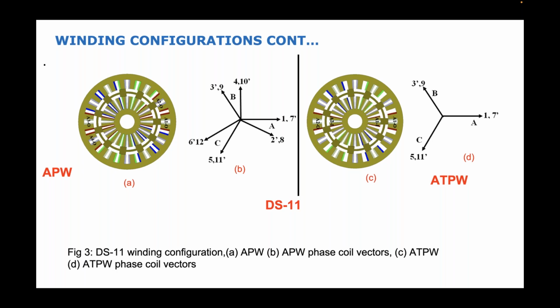For the 11 rotor pole, the winding configuration for all pole wound is shown in figure 3A, while its phase coil vector is shown in figure 3B. For the alternate pole wound, the winding configuration is shown in figure 3C, while its phase coil vector is shown in figure 3D. For the resultant voltage, just like in the 10 rotor pole, the phase voltage is the addition of the coil voltages. Next slide.